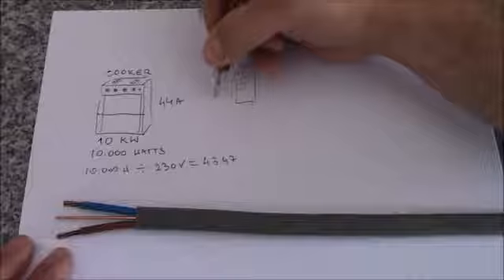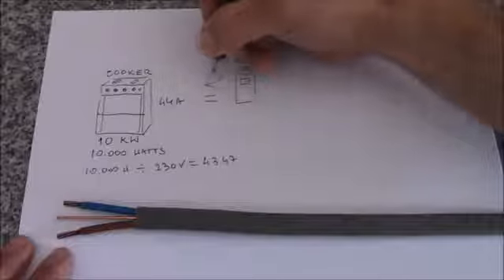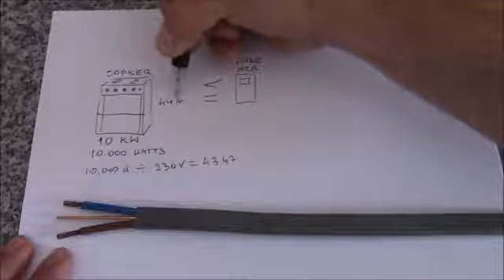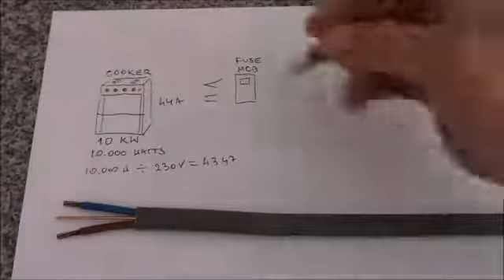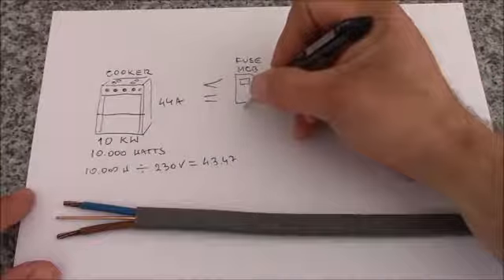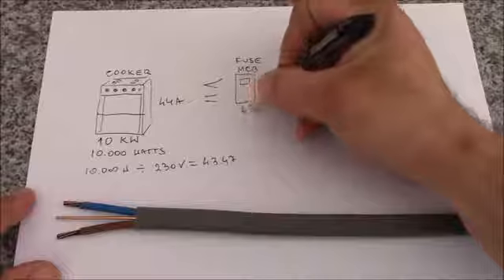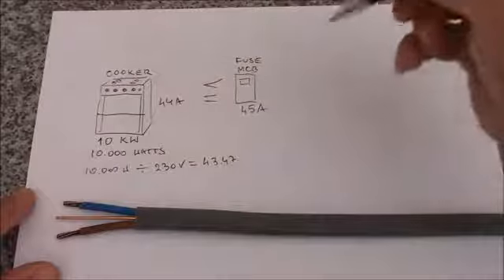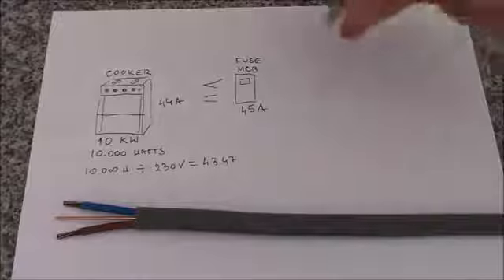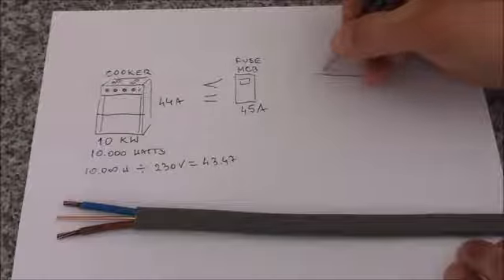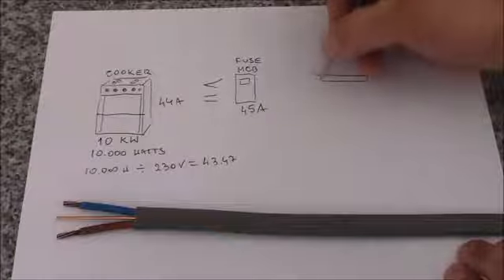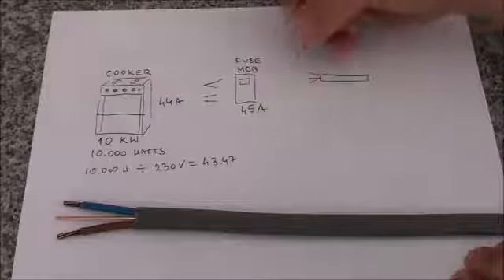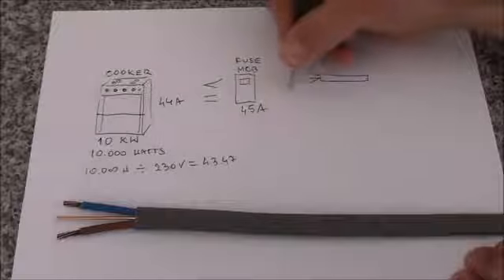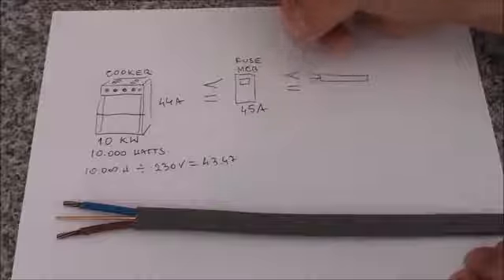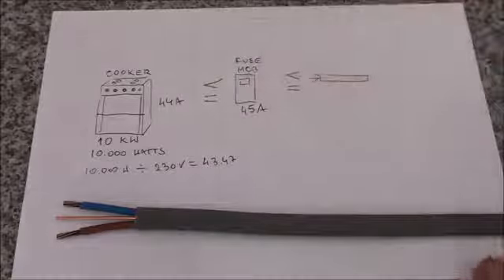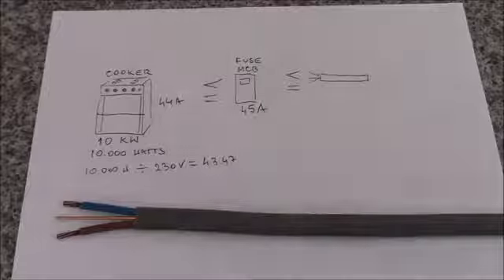And this has to be at least equal or bigger than the cooker. So we can install a 45 amp fuse or MCB. Now we need to calculate the cable. So let's say that's the cable. And the rating of the cable also has to be at least equal or bigger than the rating of the fuse. So how do we calculate it?